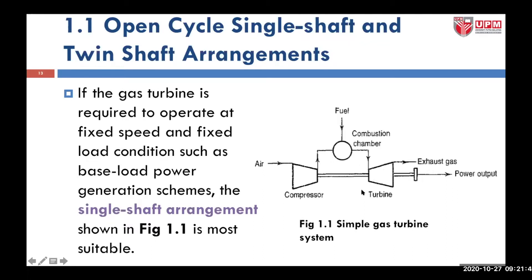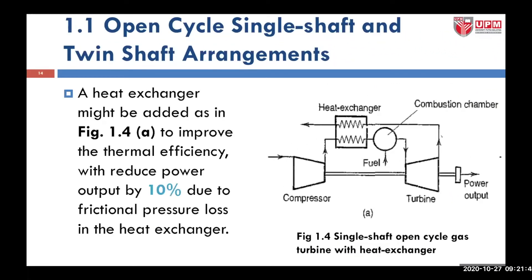In the middle we have the combustion chamber. This figure shows a single shaft open cycle gas turbine with a heat exchanger. A heat exchanger might be added to improve thermal efficiency — you want to make sure that heat losses are being utilized — but with a disadvantage of a reduced power output of 10%. This is due to frictional pressure loss in the heat exchanger, since the heat exchanger has its own performance, normally about 80% to 90% only.